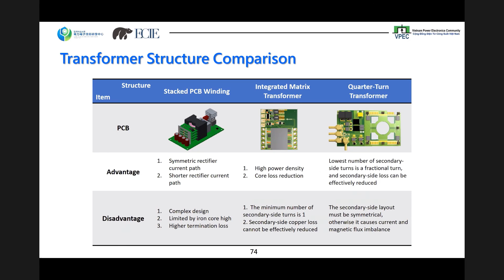Thank you for your question, it's very interesting. For this quarter-turn application, as you say, we reduce the turns ratio to 2 to 0.25. If the magnetic core size is based on the primary winding and the flux density, to keep the same flux density we need to use a larger core for this kind of design.